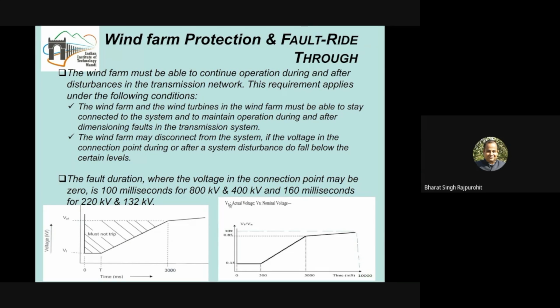So what is 0 to t seconds? It is 100 millisecond for 800 and 400 kV lines if the wind farms are connected to this voltage level, and 160 millisecond for 220 and 132 kV lines. This is what is specified. Then it says that if the fault level is persisting, the system can be disconnected. But during this curve it must not trip in that region. The characteristic is such that the system should not get disconnected.